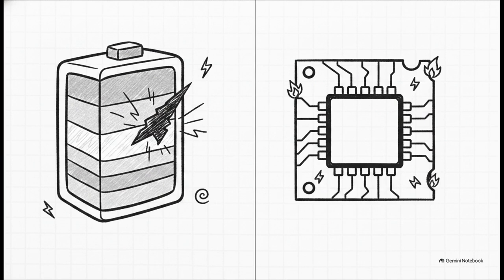But beyond just trapped heat, we also have to worry about internal electrical threats. Think of them as invisible leaks. For example, metallic impurities or tiny microscopic burrs left over from manufacturing can actually pierce the internal separators, and that causes micro short circuits. These shorts create this extreme self-discharge rate that just constantly drains the cell. On top of that, the very MOSFET chips on the circuit board that are supposed to balance the battery can suffer thermal breakdown from the constant high-temperature stress, completely knocking out their ability to fix the imbalance.